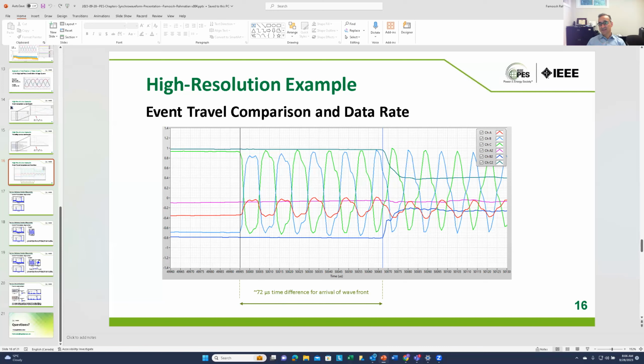But the high resolution megahertz data, even though the sensor is sampling all the time, is not usually streamed all the time. So there are triggers in the device, and when an anomaly happens, either a fast change of voltage or amplitude drop, voltage sag, voltage swell, significant frequency change, some trigger, it captures the waveform relative to that event. For example, this particular waveform you see, the device is set up so that if a fault like this happens, it captures 6 cycles before and a minimum of 9 cycles after.